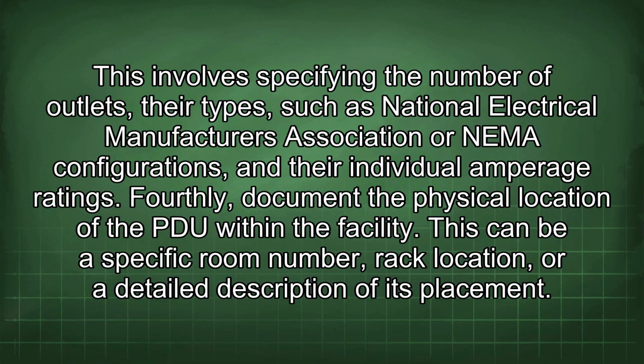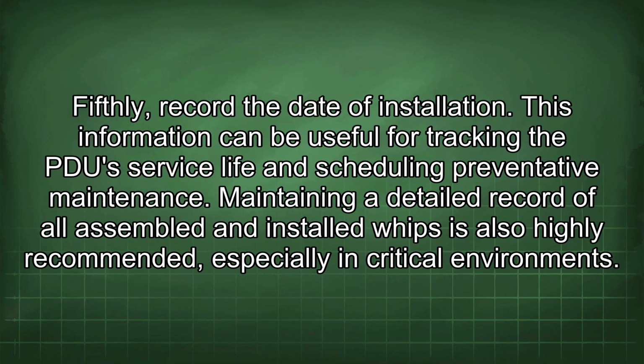This involves specifying the number of outlets, their types, such as National Electrical Manufacturers Association or NEMA configurations, and their individual amperage ratings. Fourthly, document the physical location of the PDU within the facility. This can be a specific room number, rack location, or a detailed description of its placement. Fifthly, record the date of installation. This information can be useful for tracking the PDU service life and scheduling preventative maintenance.